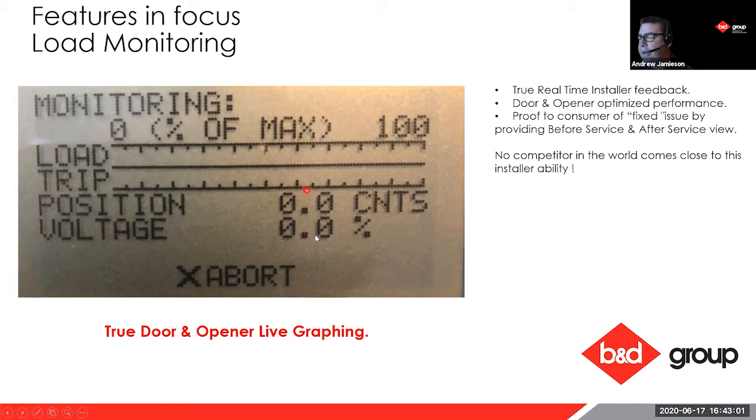It's actually opening up as curtains the full view of the site. So now there's no guesswork. If you plug this in, you'll know. To the point with granular control here, see this CNTS, you would think it's something else, but it's actually counts. It's counting constantly, right? Between open and close, there's sliced 1 millimeter increments between those 2 positions. And if you can identify your bouncing point where it's spiking load, that's a problem area, stop it.